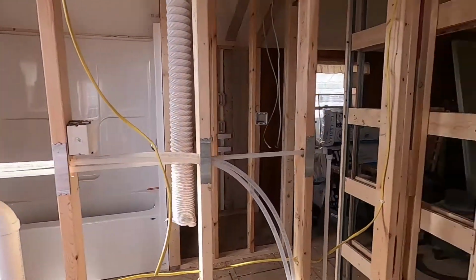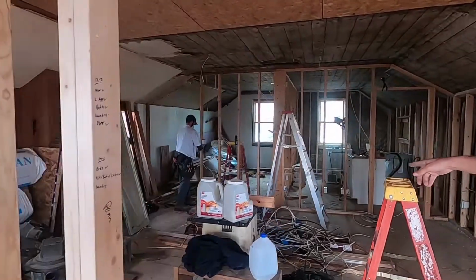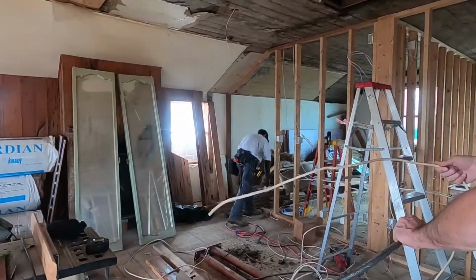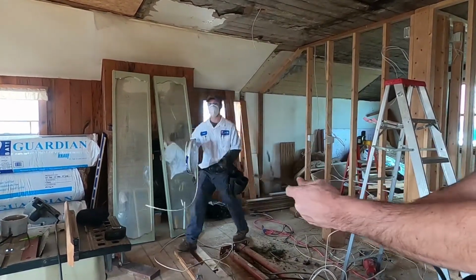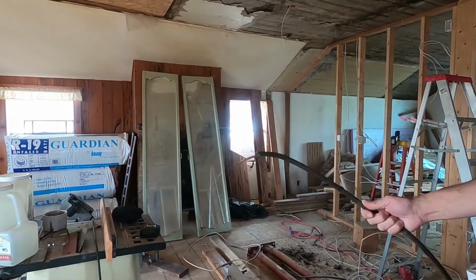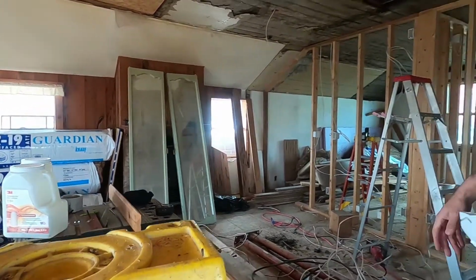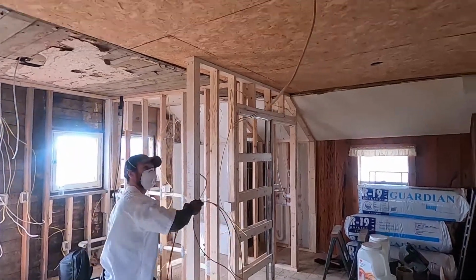So these guys, they're ripping out a lot. They left the ceilings. Some of this old wire you can see here is a mixture. This is the newer stuff we use today. It has the grounds in it, ground wires. And then you've got the old stuff, all brittle and falling apart, and that's the old wire they're getting rid of, updating it from the no-grounds. So they rip that out, and once they get that out, we'll poke in our new wires for the light.